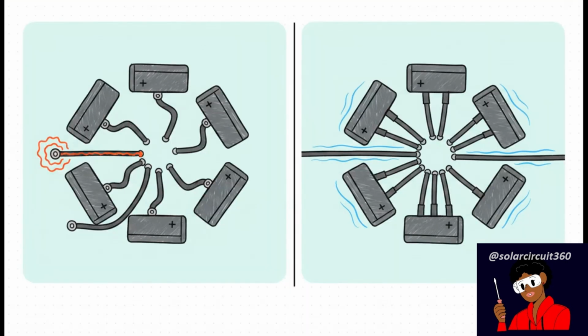And actually, it's not just the bolts. Your physical layout plays a massive role in this heat, too. If you have unequal cable lengths and varied torque across your battery strings, it physically forces unequal current sharing. Basically, one battery string ends up working way harder than the rest, which accelerates system imbalance and skyrockets that localized heat. But if you aim for the ideal setup, meaning perfectly equal cable lengths and every single terminal torqued strictly to manufacturer's spec, you ensure perfect parallel current sharing. This prevents any single battery string from sweating too hard and keeps the entire system balanced and, most importantly, cool.